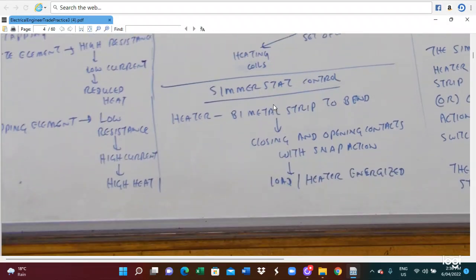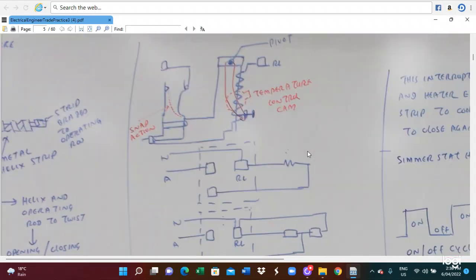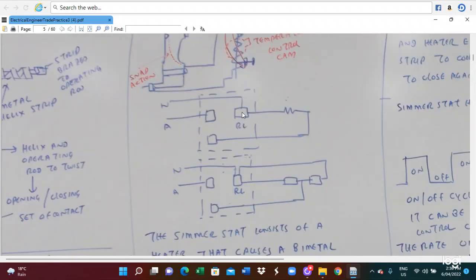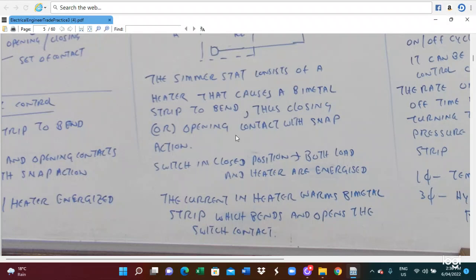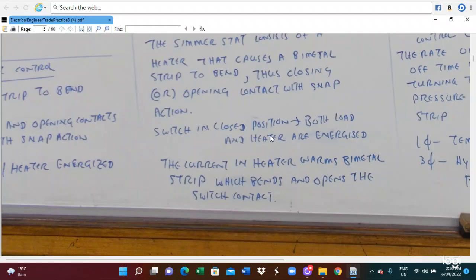We also utilize a simmerstat control. The heater includes the bimetal strip to bend, closing and opening the contact with a snap action, and then the load and the heater are energized. So here is the connection of the snap action and the temperature control switch diagram and its connection diagram. The simmerstat consists of the heater that causes a bimetal strip to bend, thus closing or opening the contact with snap action. Switching in the closed position, both load and heater are energized. The current heats the bimetal strip, which bends and opens the switch contact.